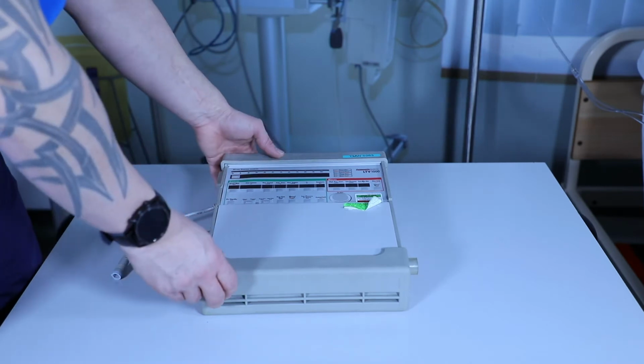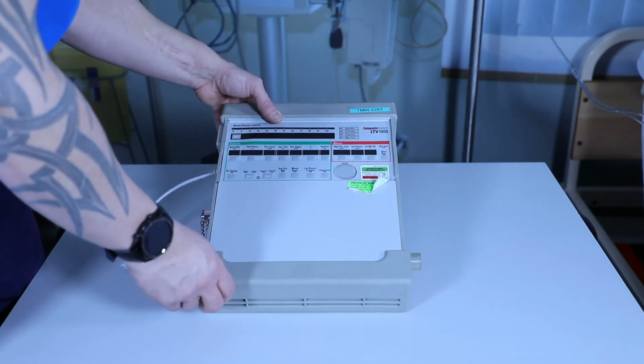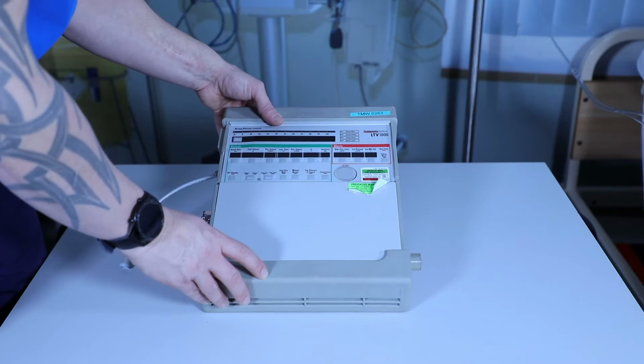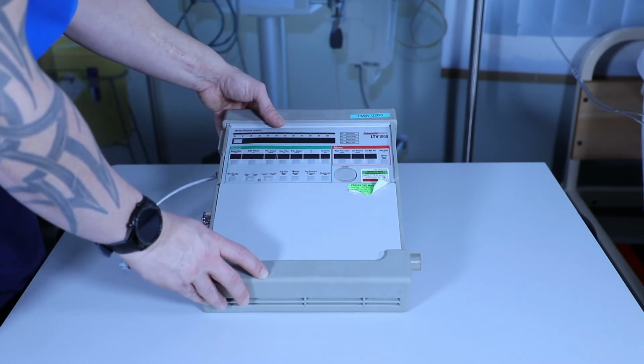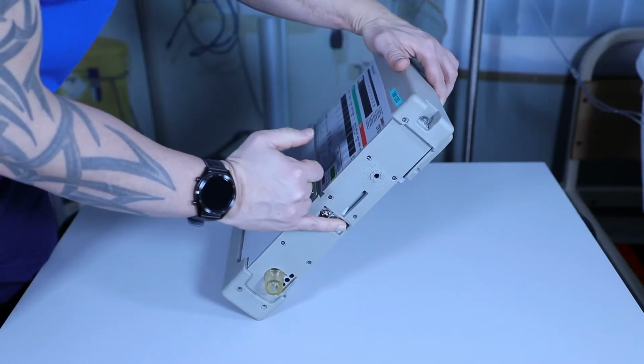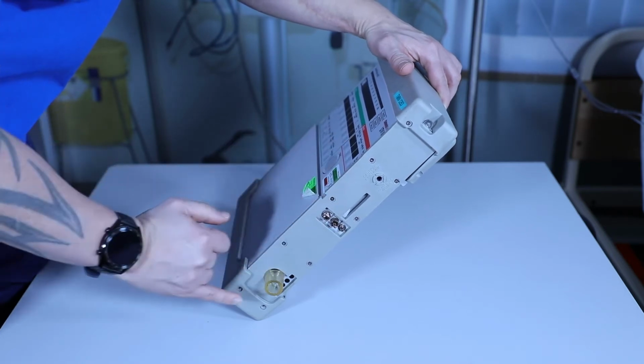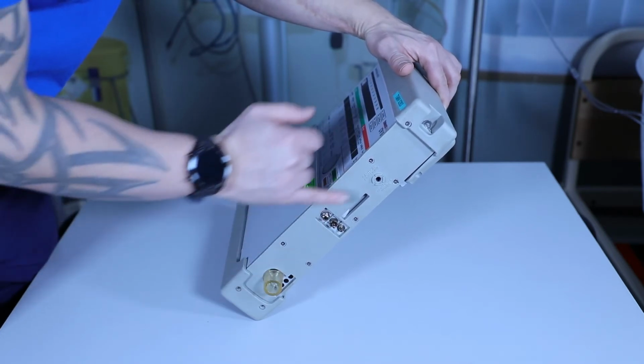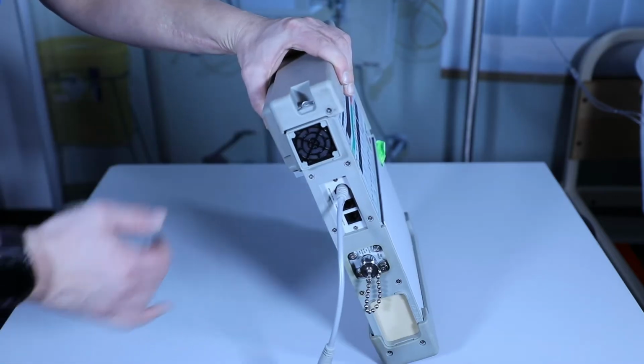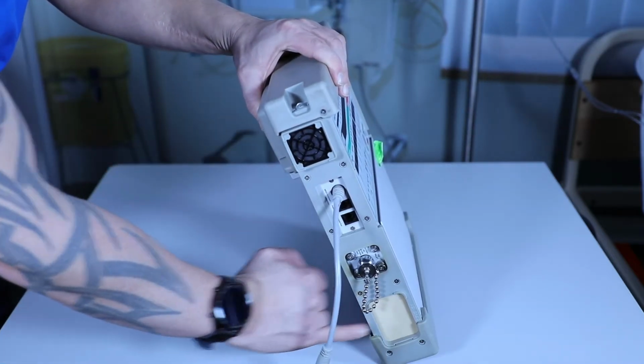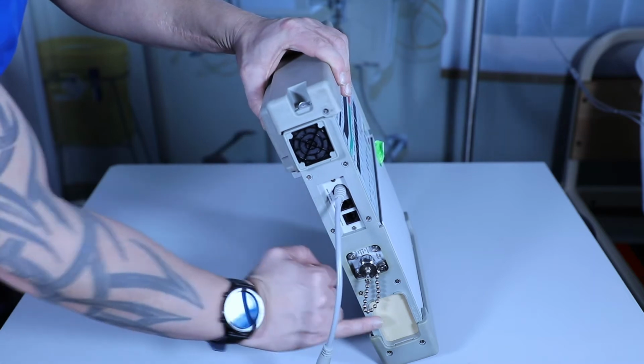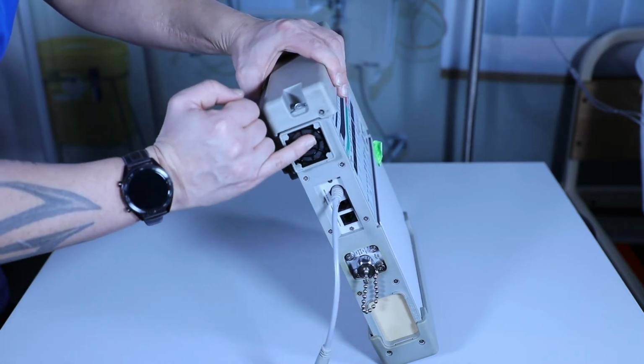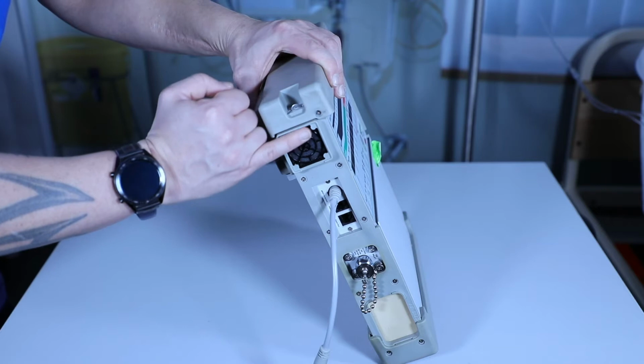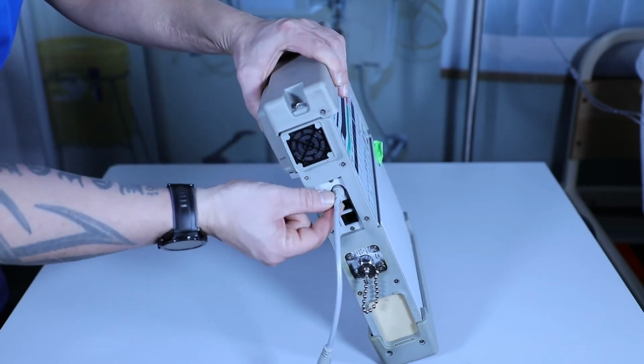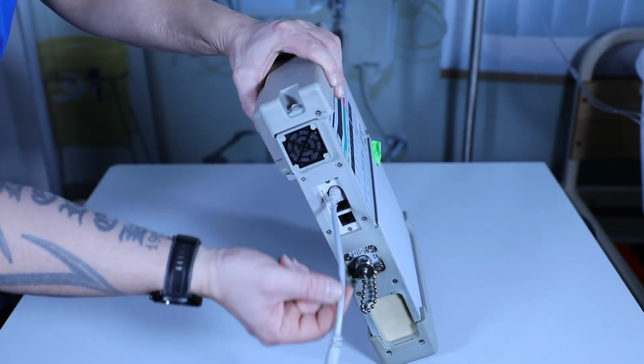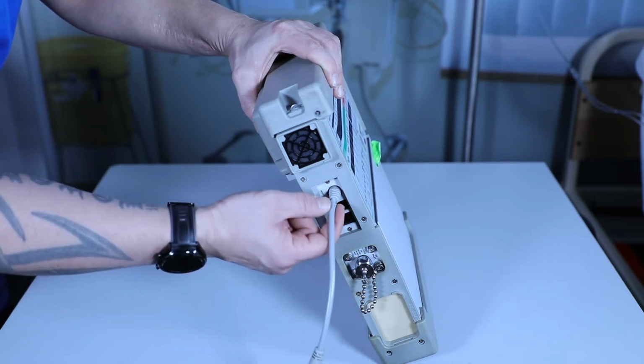We're then going to look at the LTV itself. We're going to give this a thorough look over, inspecting it for any obvious signs of dirt, dust or damage. Looking at the right side of the LTV, we can see a few of the sensor ports here, which we'll go into in more detail, the patient circuit port and then the speaker. On the left side of the device we can see the air and the fan filters. These filters, both of them have to be replaced every 30 days. The air filter is notoriously difficult to remove the plastic casing, so please be careful with this. We then need to inspect the power connection port, ensuring that there is no exposed wire.